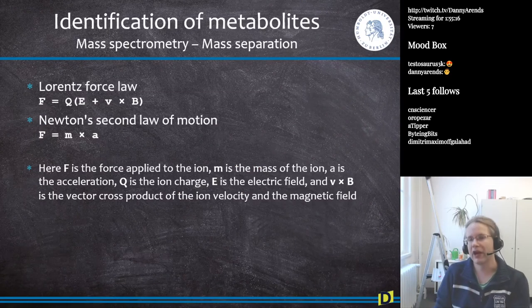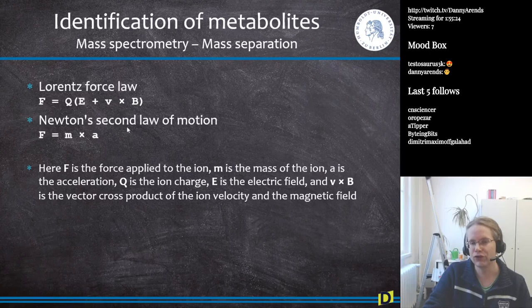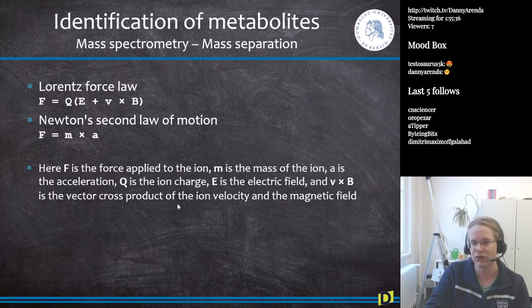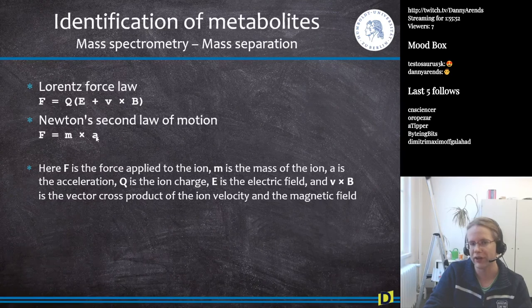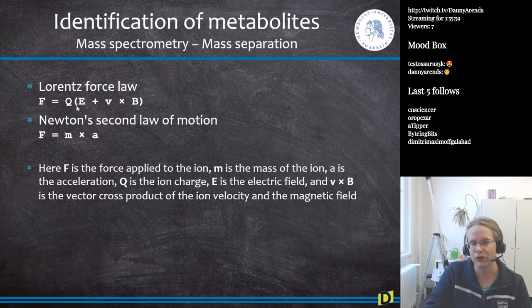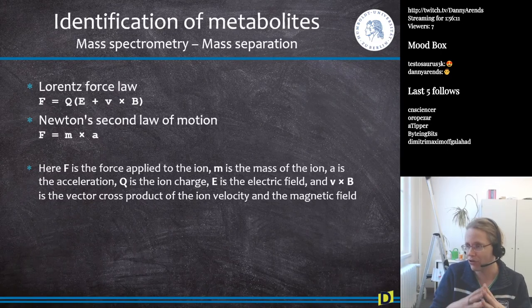Mass spectrometry is based on two fundamental physical laws: the Lorentz force law and Newton's law of motion. F = MA, where F is the force applied to the ion, M is the mass, and A is the acceleration. Additionally, the force equals Q times E plus V cross B, where Q is the ionic charge, E is the electric field, V is the ion velocity, and B is the magnetic field. These two laws underpin mass separation in the instrument.